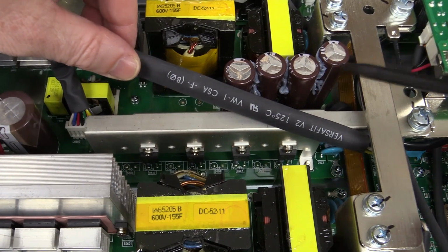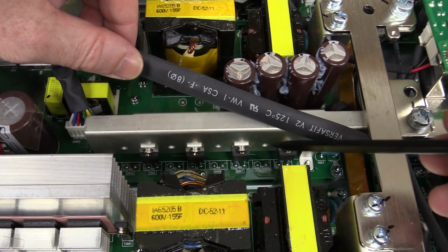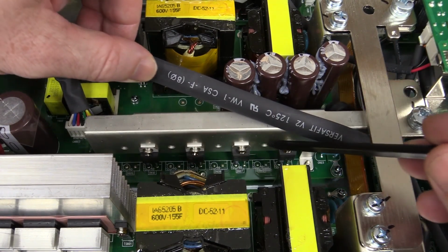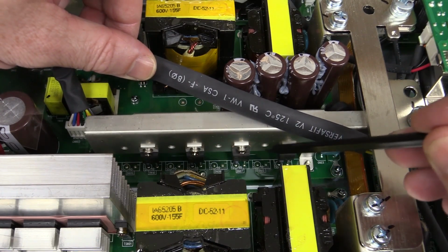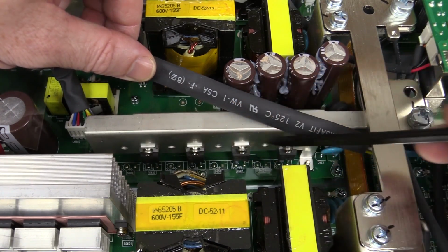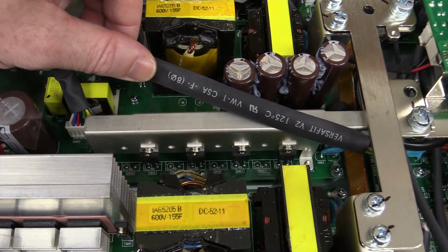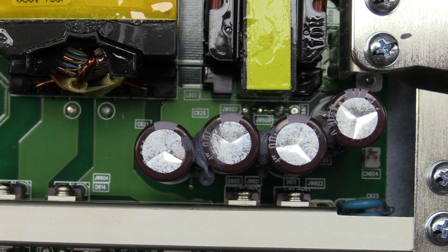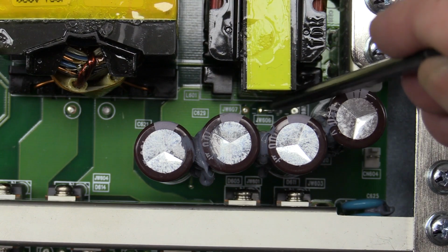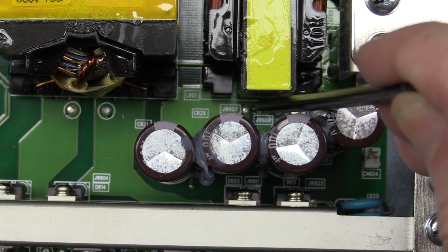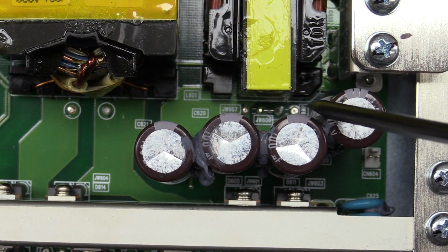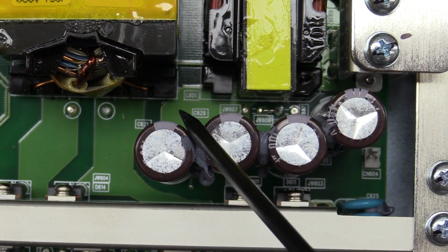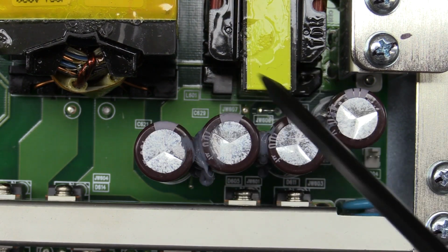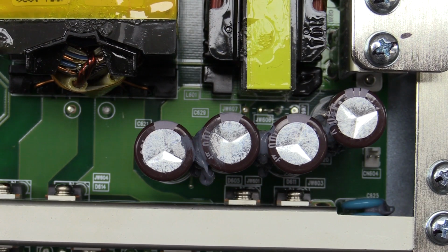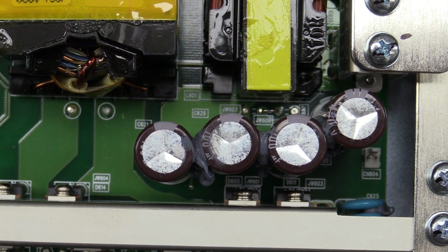And you can see here that on the secondary side, in addition to the 4 other diodes on the other side of the bus bar here, there's provision for another 4 in there, so that'd be for a higher current model. And I think you can see down there, there's a jumper in one position, and that would be to configure these output capacitors in series or parallel combination for, once again, the different voltage and current models.